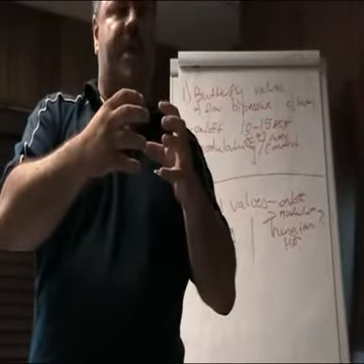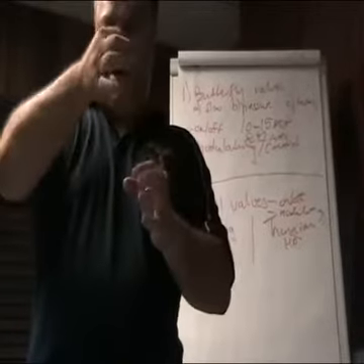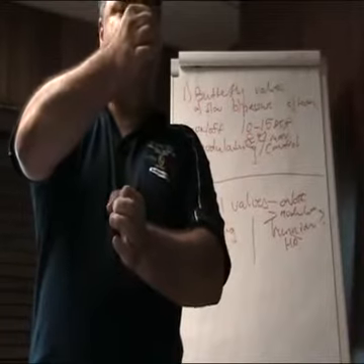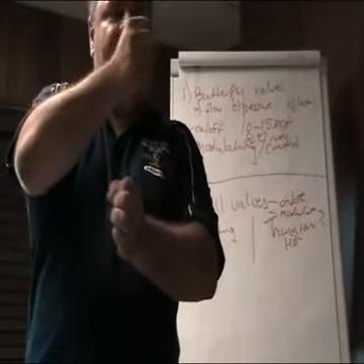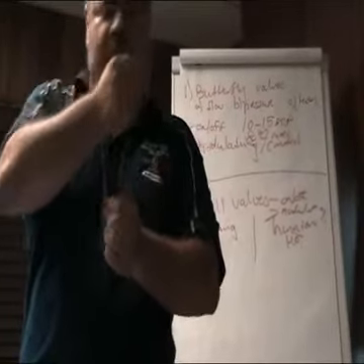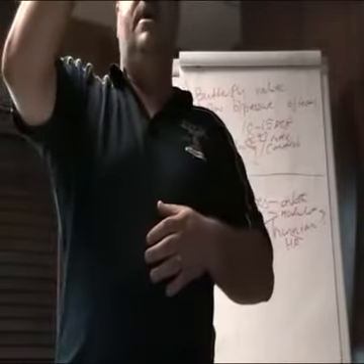When you get to the high pressure stuff, which is the trunnion mount, you've got a ball that has a little shaft on top and at the bottom, that is the support for high pressure and high temperature applications. For the vibration, it's just more support. It's basically extra metal. So this is what the ball looks like. You turn it like this, 90 degrees, closes your application, opens your application. This is a normal floating ball.